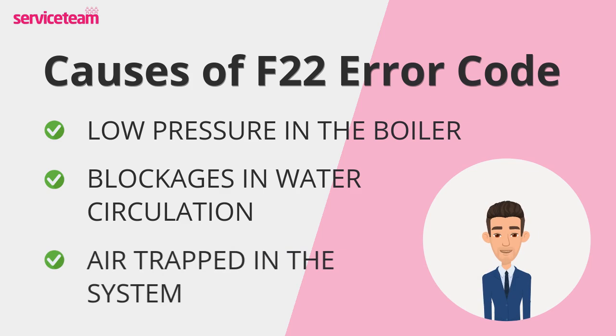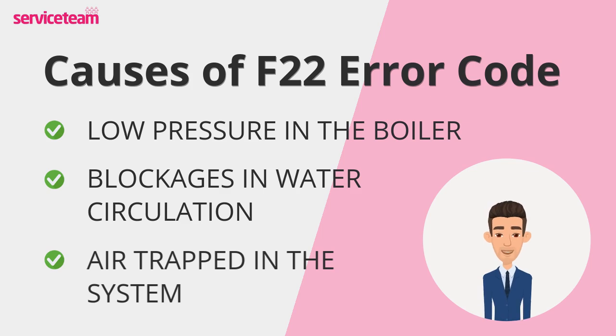Trapped air in the system can also cause the F22 fault. Air bubbles in the pipes can disrupt water flow and pressure. This often happens after bleeding radiators or if there's an airlock in the system. The boiler may register low pressure because of this air, resulting in the F22 error code.